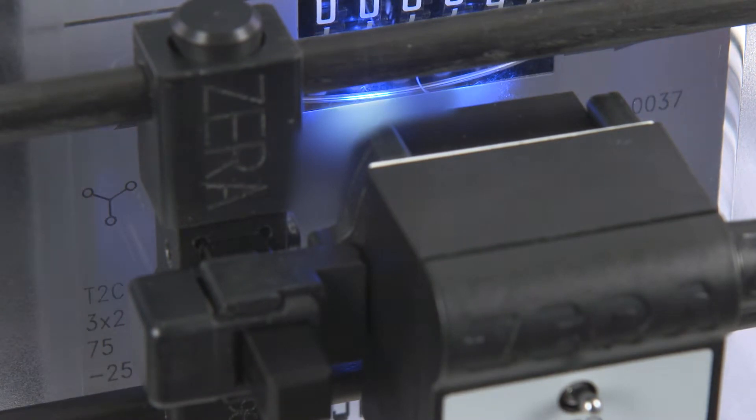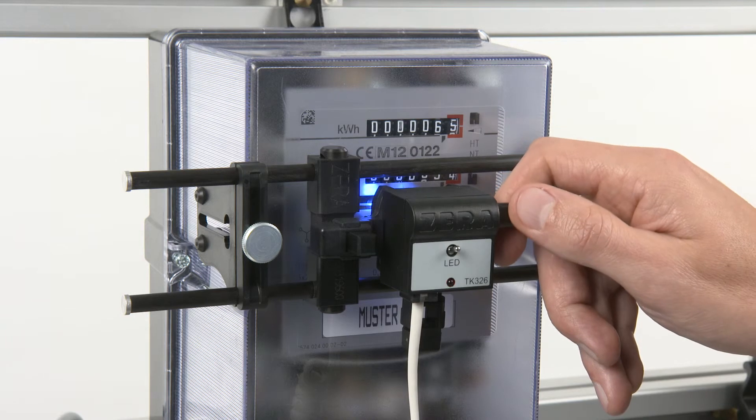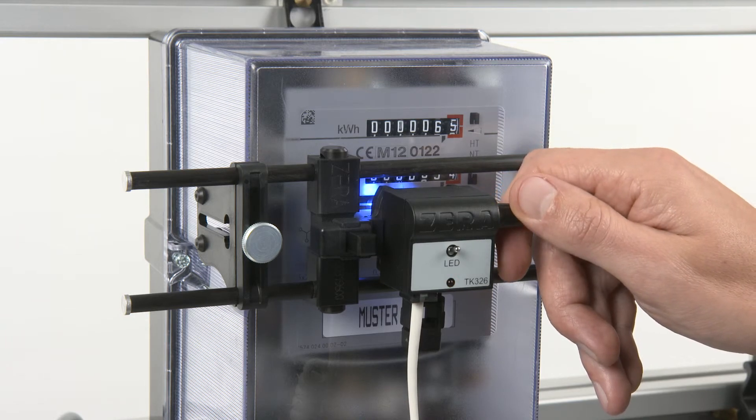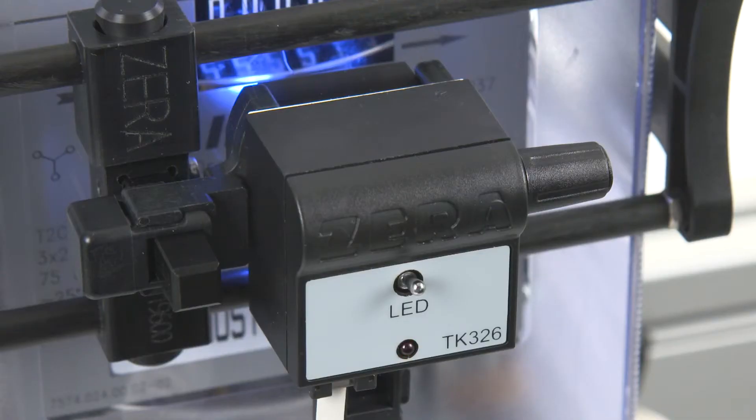After that, adjust the sensitivity of the scanning head again. Pay attention that the scanning head does not detect multiple pulses. In this case, adjust the potentiometer again. Verify the setting by a complete rotor turn.